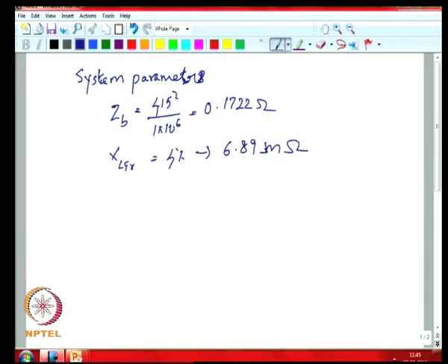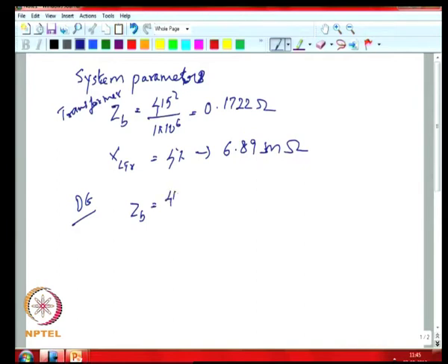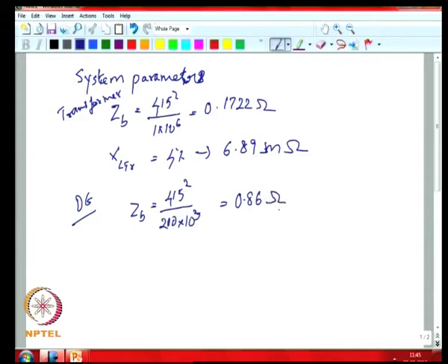If you look at the DG, the Z_base for the DG—it is a 200 kVA DG—so the base impedance is 0.86 ohms. With the effective leakage of the DG being about 10 percent, that corresponds to 86 milliohms.